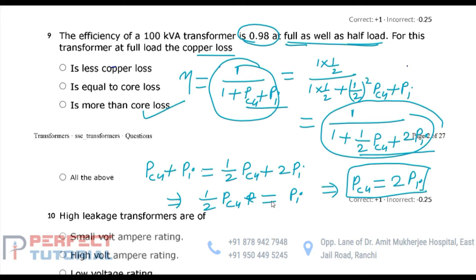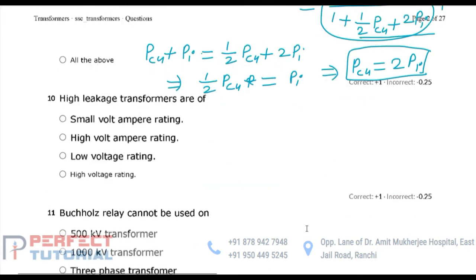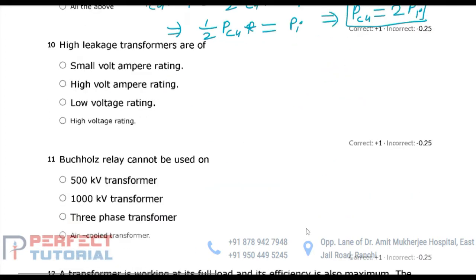Next, high leakage transformers are of. Say transformer's kVA rating is inversely proportional to leakage impedance. So high leakage transformer means having a high leakage impedance. So if leakage impedance is larger, then kVA rating obviously would be smaller. Means high leakage transformers are of small kVA rating or volt ampere rating.